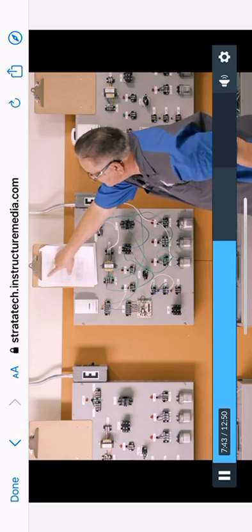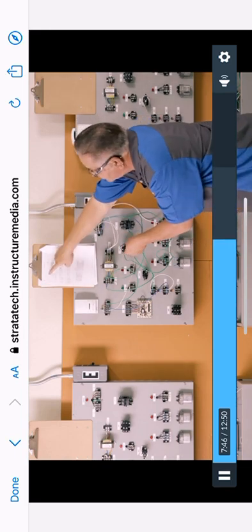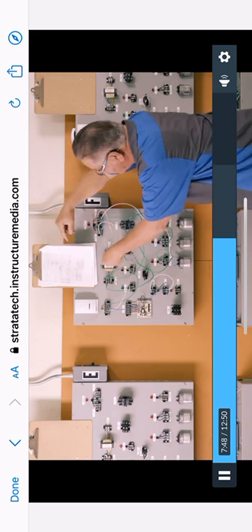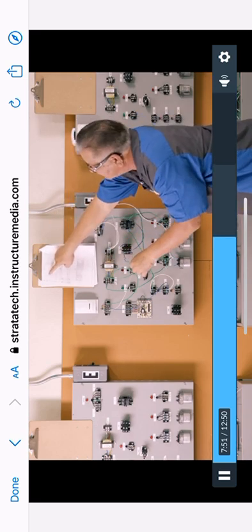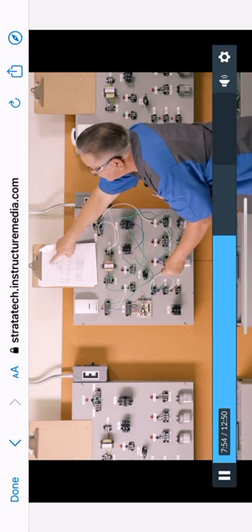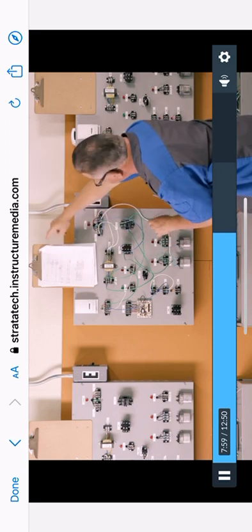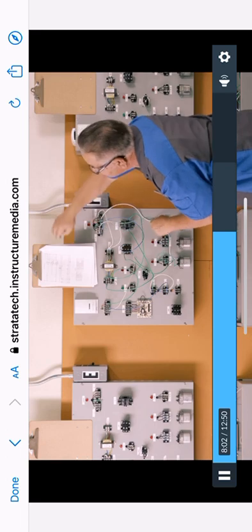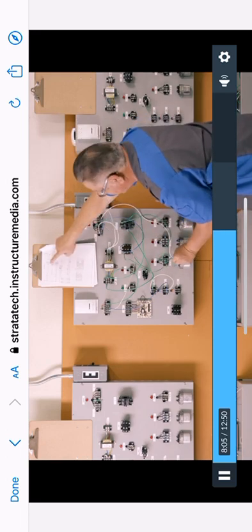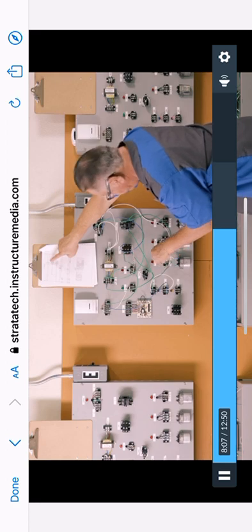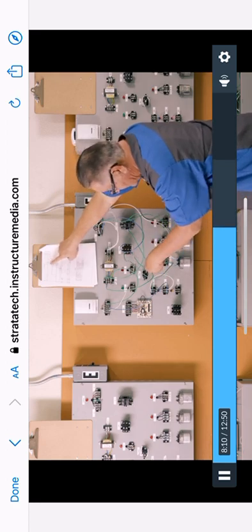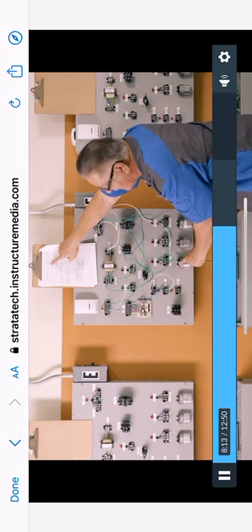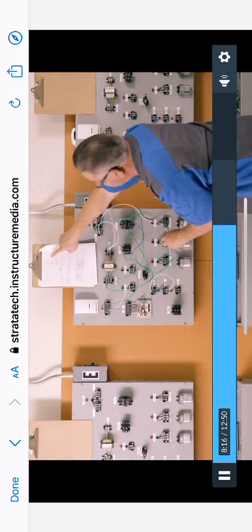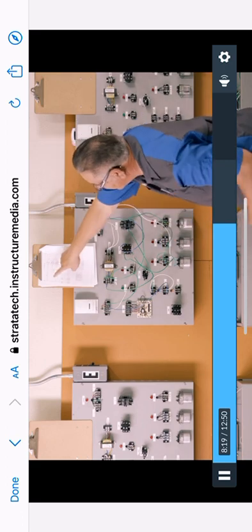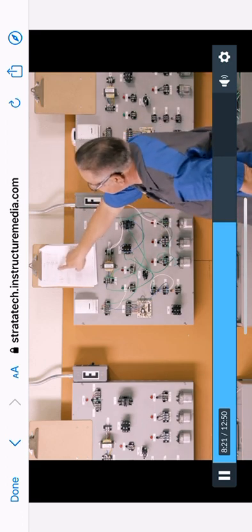I went from line 1 to my normally open switch on my indoor fan relay, which is the blue wire I got in my hand right here. I came out of my indoor fan relay. I went to my common on my indoor fan motor. I came out of my R terminal, and I went straight to line 2, which is this green wire I got in my hand. I went from my start cap, which is this one here, and I went straight to my cap. I came out of here. This is that green wire I got in my hand right now, and I went to one side of your cap. I came off the other side of the cap, and I'm going back to line 2. That is complete. Now I'm going to do the outdoor fan motor compressor.